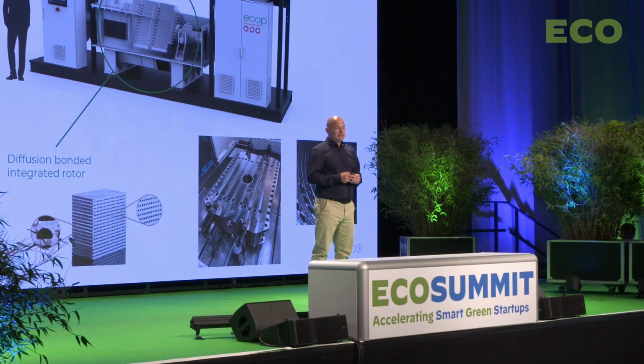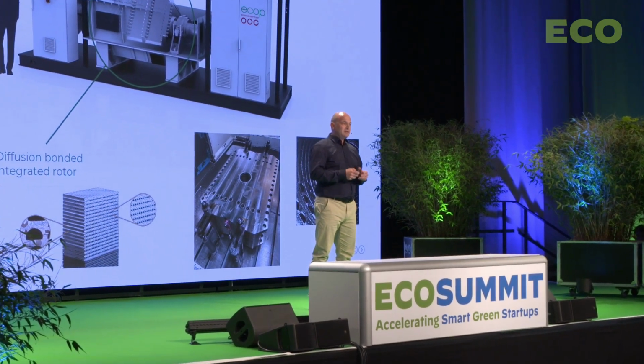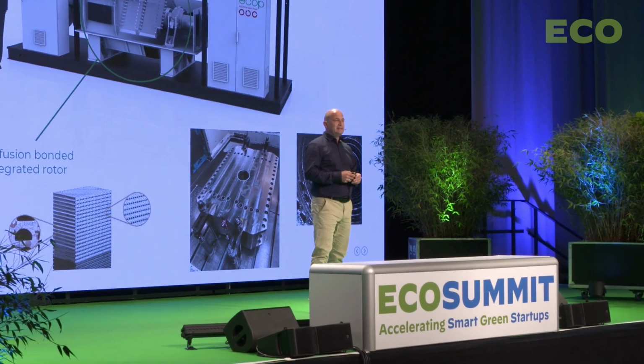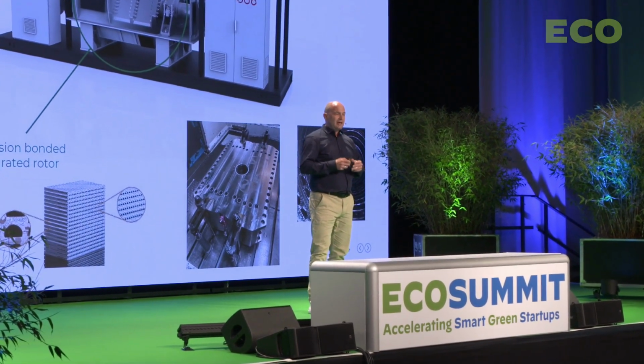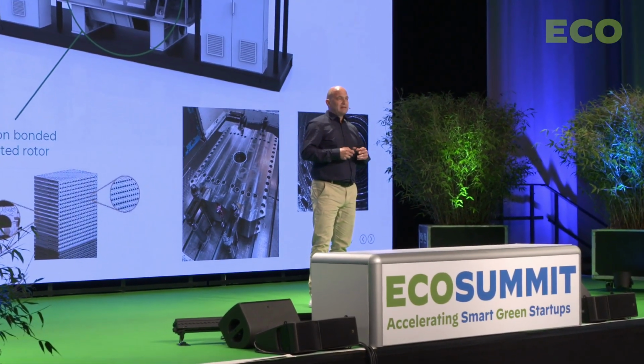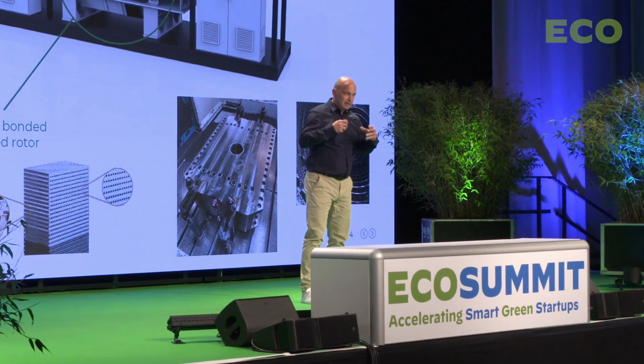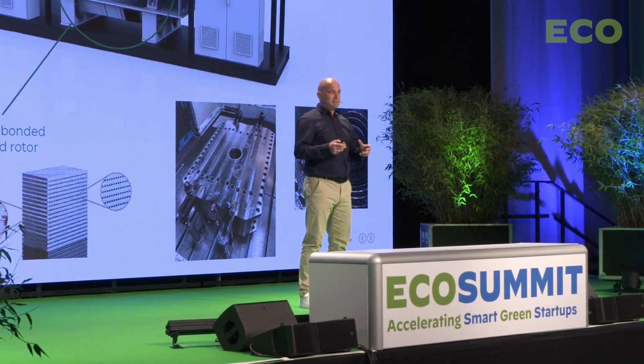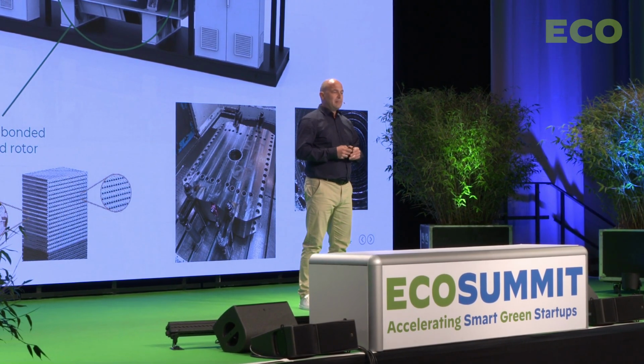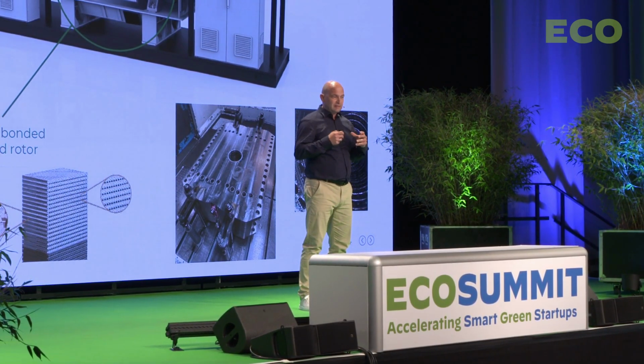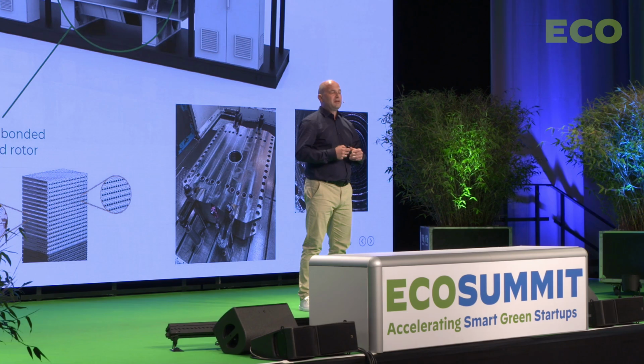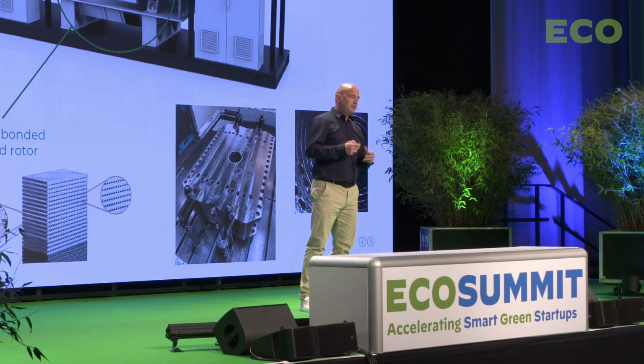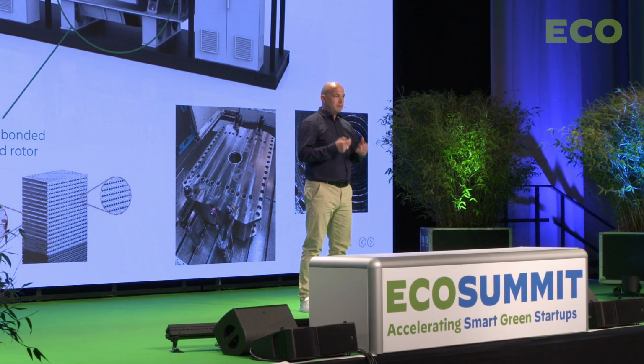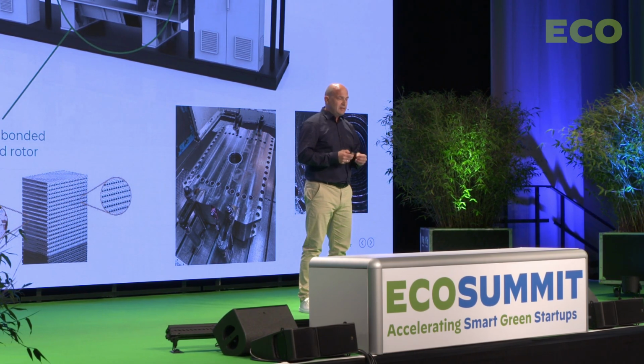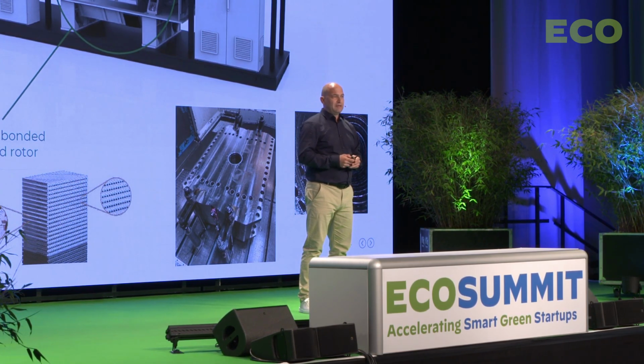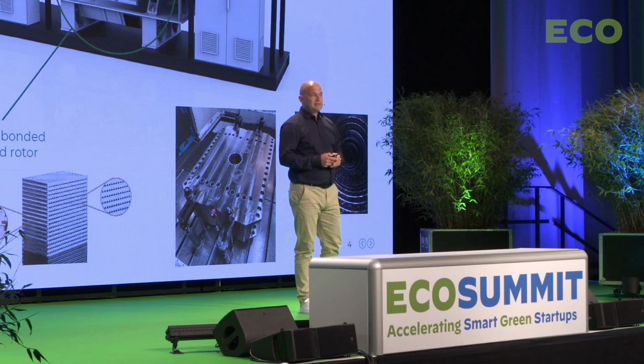More interesting is that in our latest version we produce the rotor with a technology called microchannel diffusion bonding. This has been used for decades to produce the best heat exchangers in industry, and we now use it to realize our rotor and include the entire thermodynamic cycle for our heat pump. This gives us a rotor strong enough to turn at 3,500 to 4,000 rounds per minute, realizing specs that are really exceptional for a heat pump.